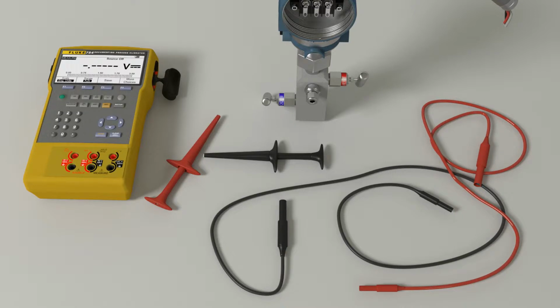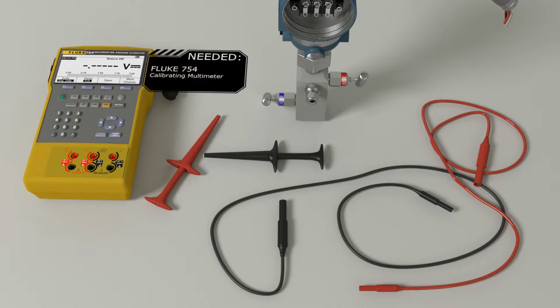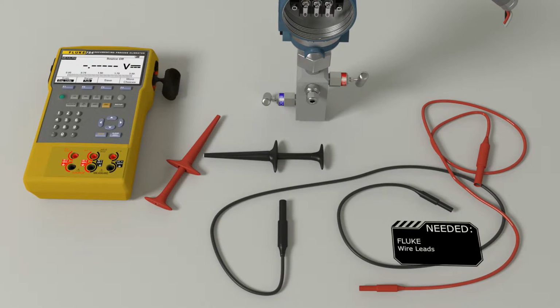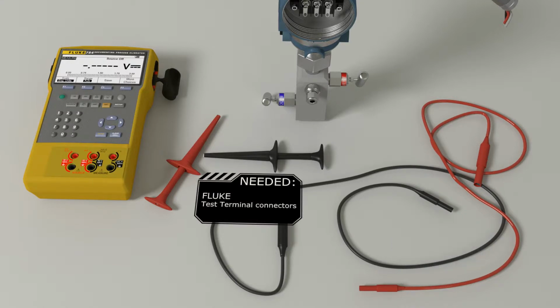In this video, we're going to discuss the tools and procedures for making our electrical connection to a pressure transmitter for calibration. For this step, you will need the Fluke 754 calibrating multimeter, referred to as the 754, a red and black female-to-female wire lead for the Fluke meter, and a red and black test terminal connection for the meter to connect to the transmitter.